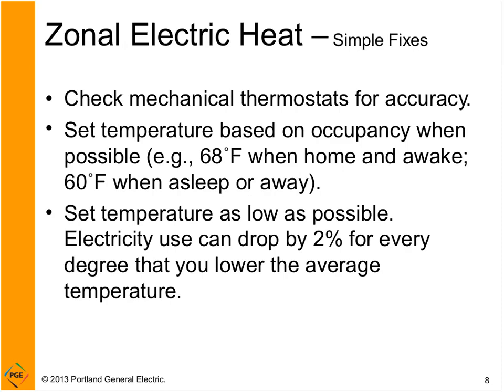So there are some simple fixes for zonal electric heating systems. One thing to check for is the accuracy of mechanical thermostats. Sometimes over time, these thermostats become inaccurate. So you can verify the setting and temperature with an additional, newer digital thermostat or thermometer, and consider replacement if these aren't accurately setting the temperature that's desired.